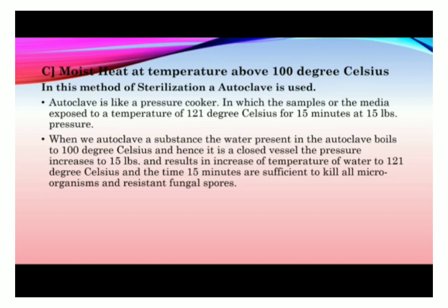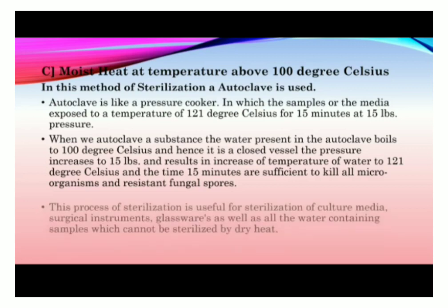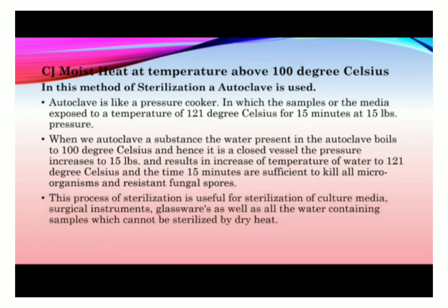Now we close the autoclave. It is a closed vessel. The pressure increases to 15 lbs, due to which the temperature of that water also increases to 121 degrees Celsius, and these things are kept for 15 minutes. This time is sufficient for killing all the microorganisms as well as the resistant fungal spores. This process of sterilization is useful for sterilization of culture media, surgical instruments, glasswares as well as all the water containing samples which cannot be sterilized by dry heat.